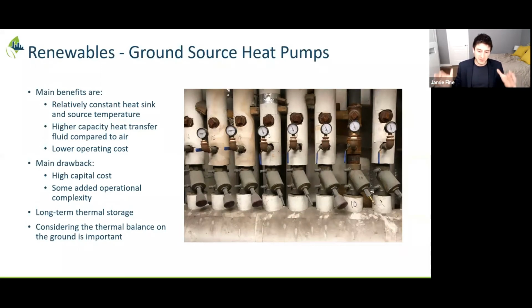And then again, this is thermal storage, and this comes back to what we said before about any energy recovery. You want to make sure that during, let's say, the summertime, you have a bunch of cooling loads in your building. You can start filling the ground with some heat, such that during the winter time, when you have heating loads in your building, you can start pulling that heat back out. So there is an opportunity here, at least in ice rinks, that you can start making sure that on the annual basis, you're taking that heat that would otherwise be sent out using your chiller, or you'd have to be adding heat during the wintertime with a boiler. The ground source heat pump would allow you to save that heat and avoid using those auxiliary systems.